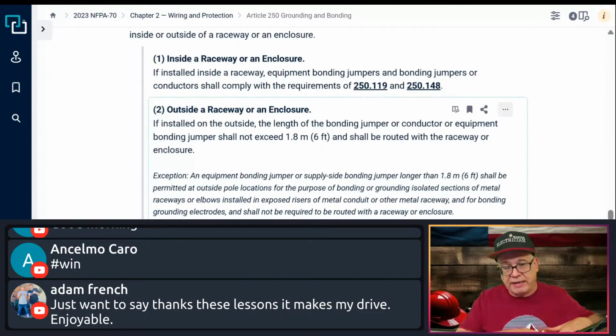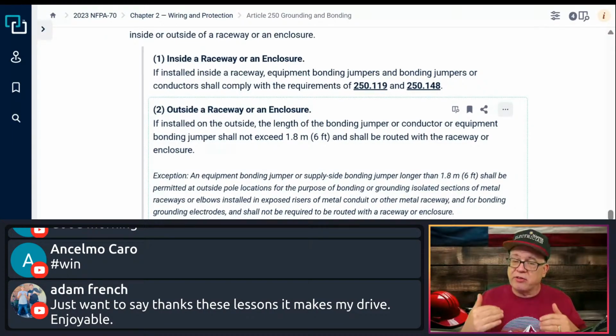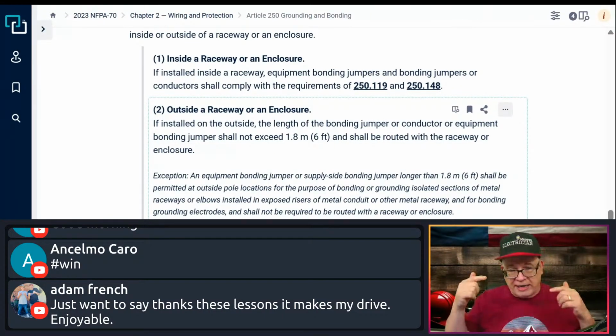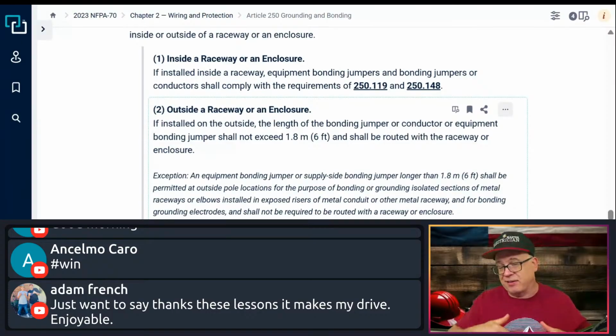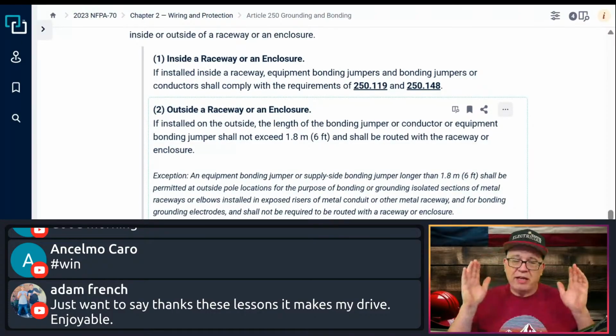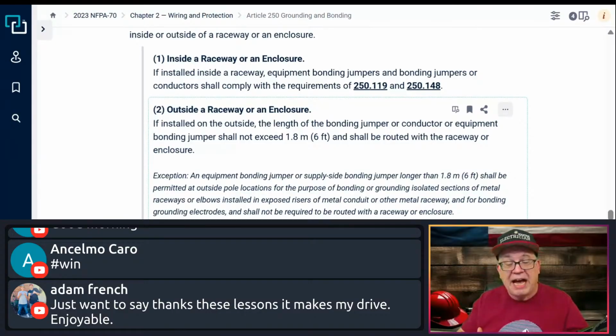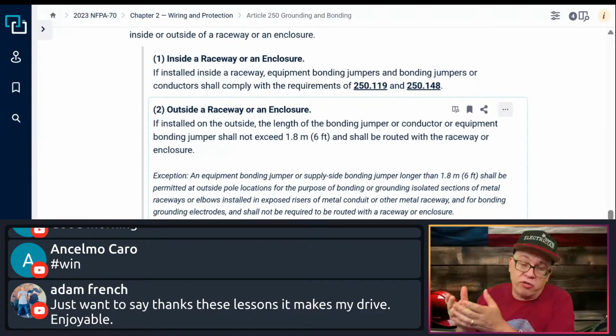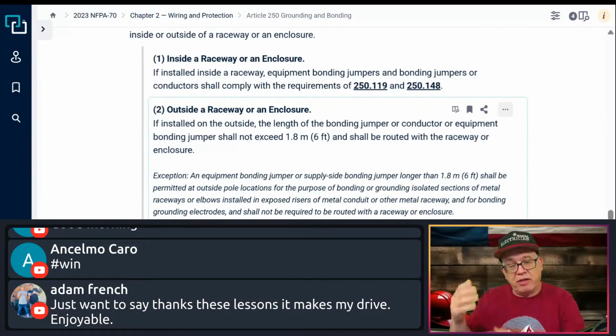They're below grade. So you sometimes might have a PVC raceway, and you have a metal 90 because, again, pulling conductors through it could burn it out. In that scenario, that metal, if it's below 18 inches, you would not have to go try to bond that elbow, it's isolated in the ground, 18 inches deep. You don't have to seek that out to make it. But if you have a metal one coming out of the ground, I encourage you to use PVC. If you have metal coming out, then you still have to bond it, that type of thing. So that's kind of what it's talking about.